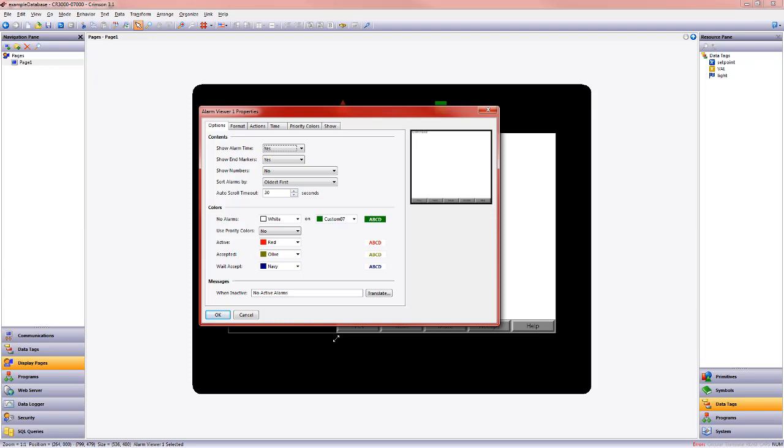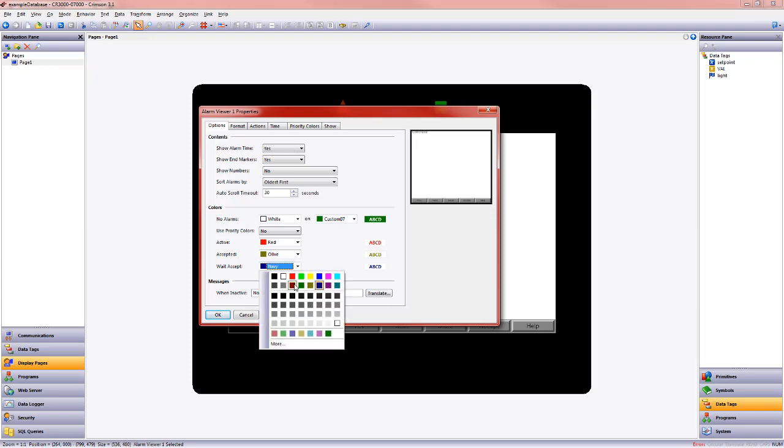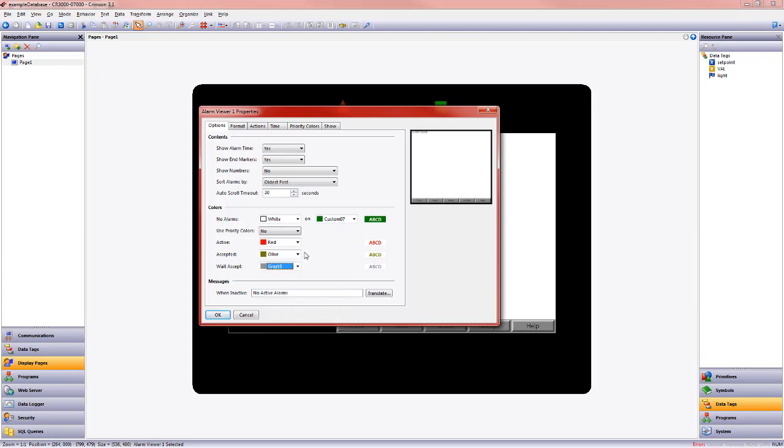For today's exercise, we're going to stay on this options tab. We want to show the time that the alarm occurred, and we can choose the colors for our alarm. In this case, let's have the active alarm remain red, but rather than navy for our wait accept, let's make it a light gray. This really emphasizes that this is the active alarm. In the case of wait accept, an alarm event occurred. It is no longer true, but we want to let the operator know that it did happen.